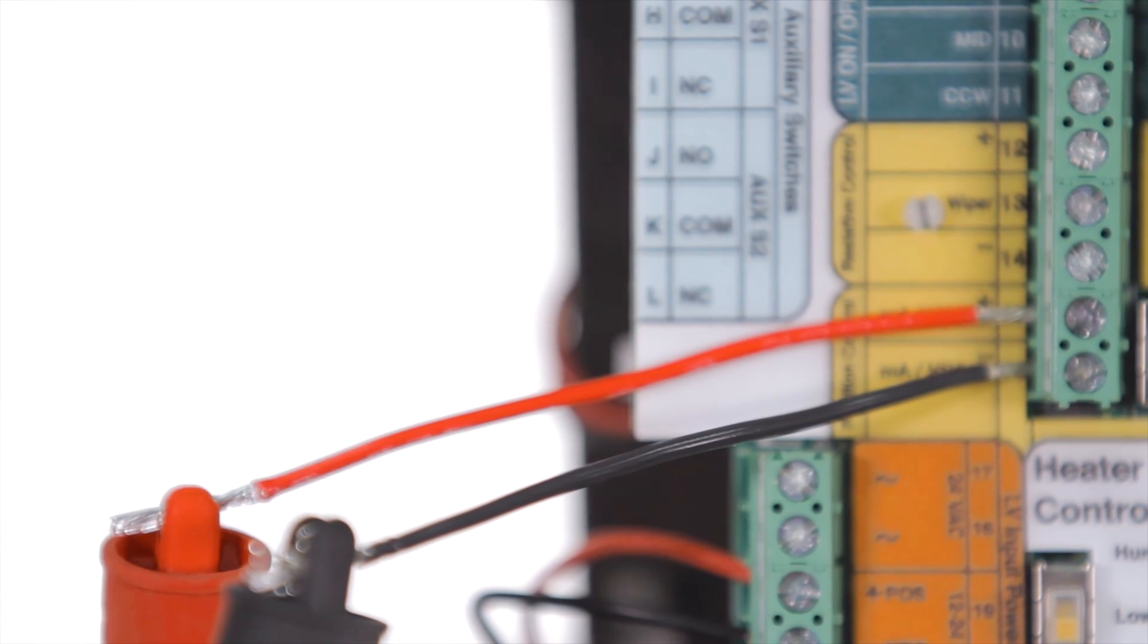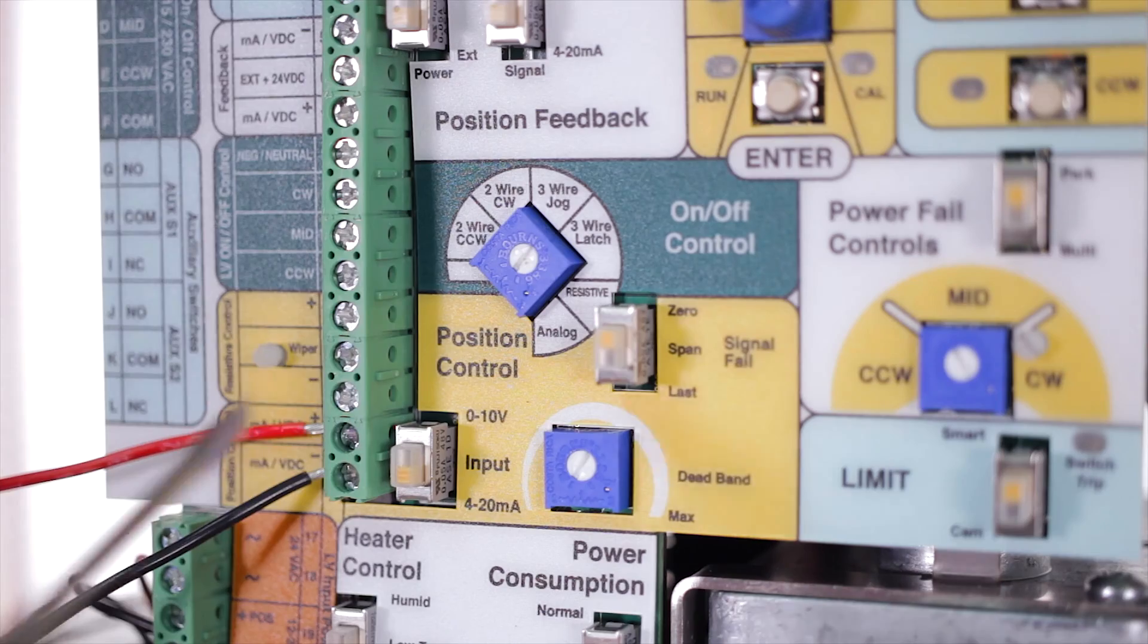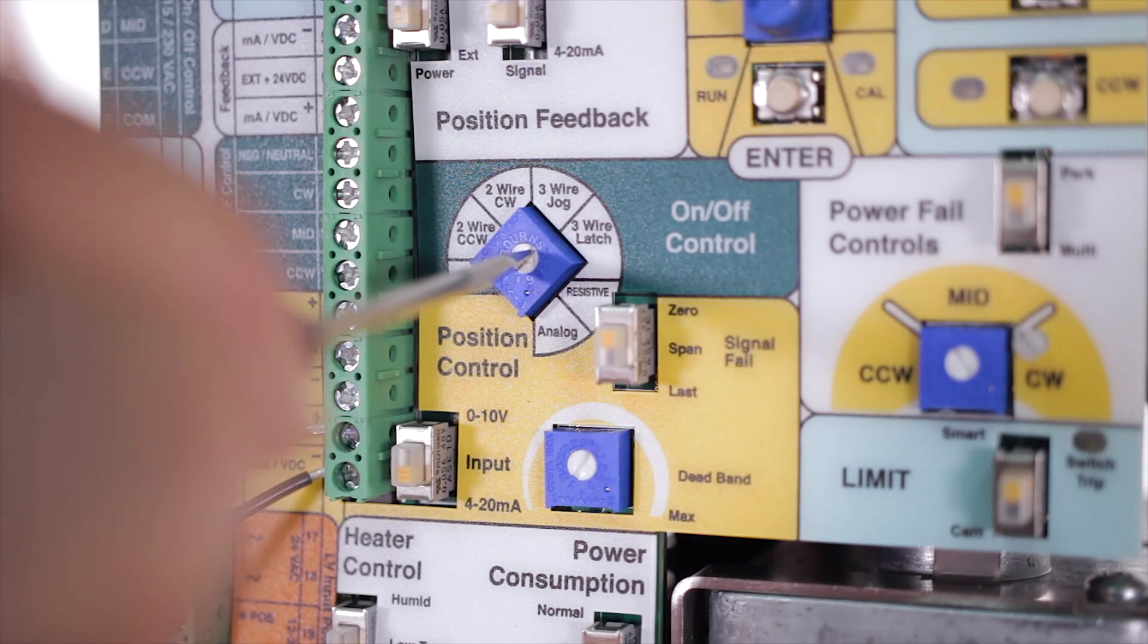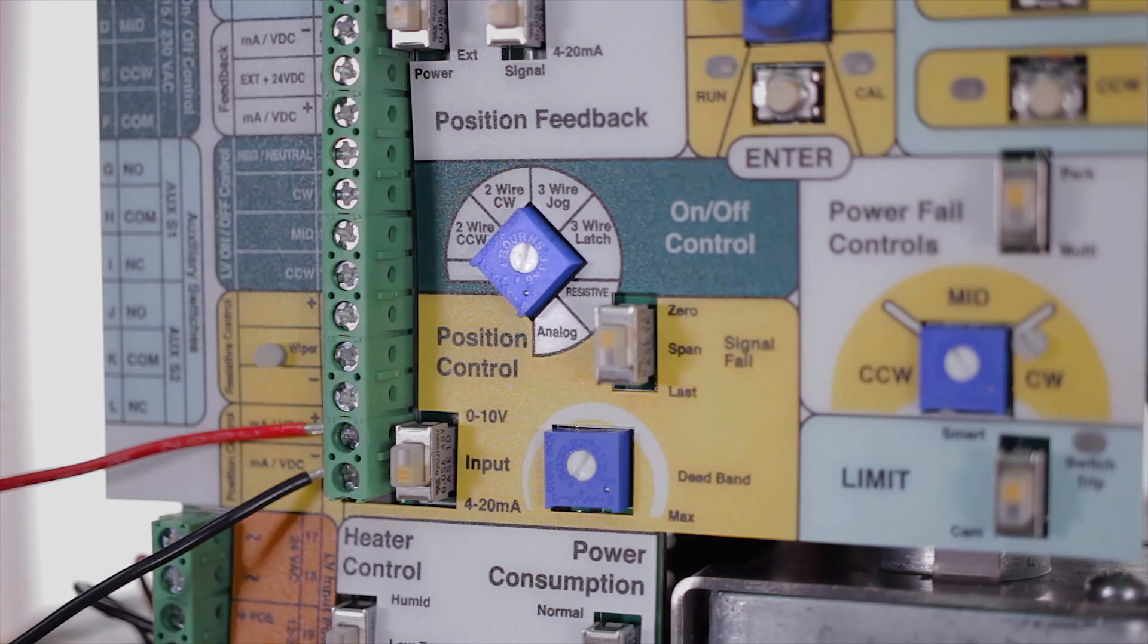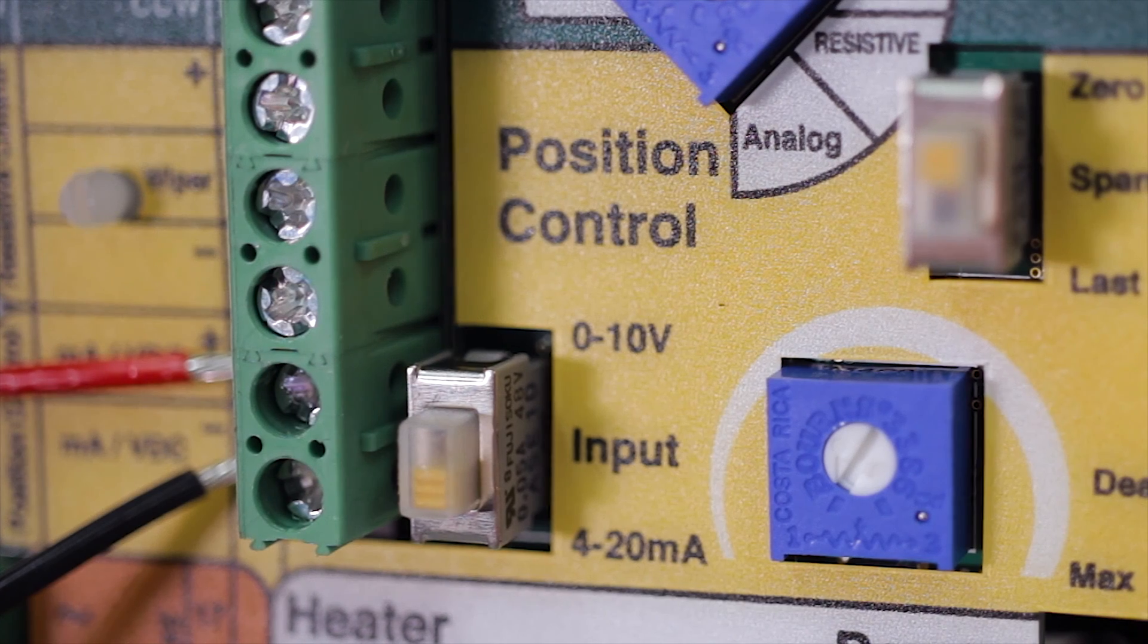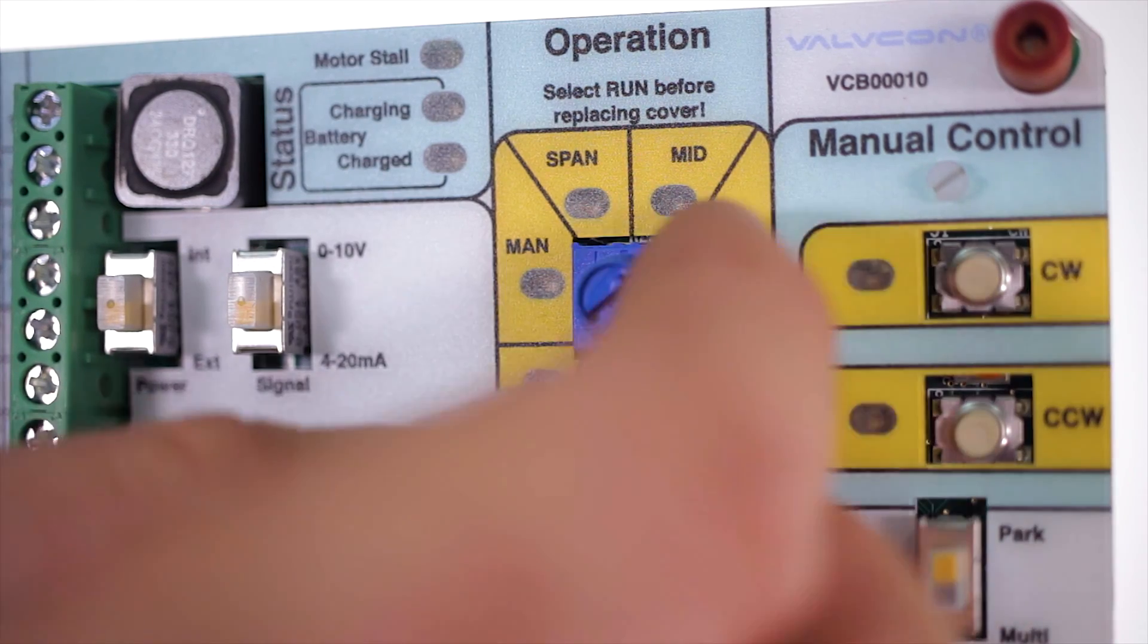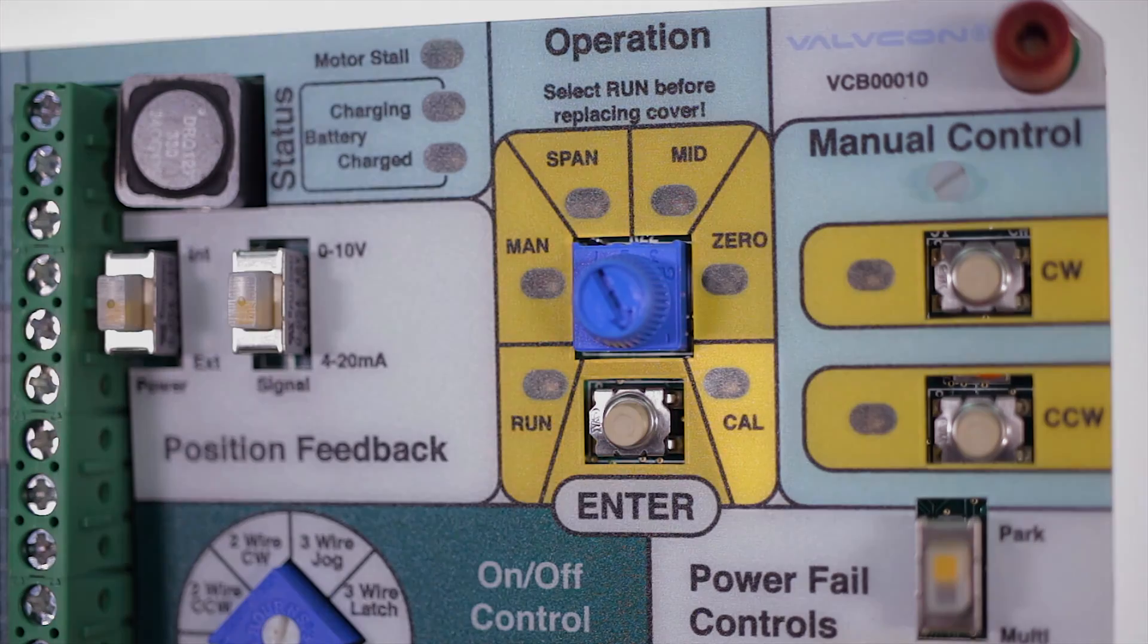We're using an analog signal but it also has modbus and discrete signal capabilities. Turn the on off control mode selector switch all the way clockwise to the analog setting. Make sure that your position control switch is on the 4 to 20 milliamp setting. Now turn your operation mode selector switch all the way clockwise to the calibrate setting.